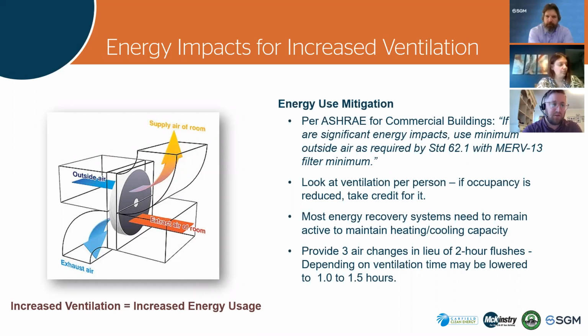Some other notes here on ways we've been able to mitigate this energy use a little bit is to consider your occupancy. So most buildings are going to reduce occupancy. Let's look at that CFM of outside air per person in addition to just per normal occupancy. So if you have 30% outside air and you're at 50% occupancy, you're probably doing really well.